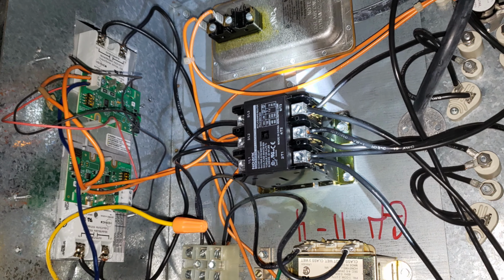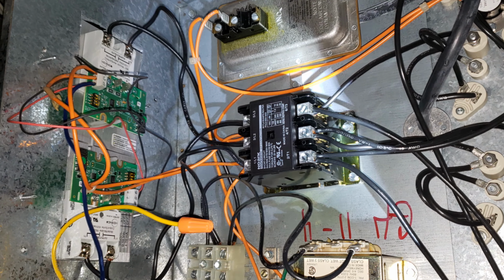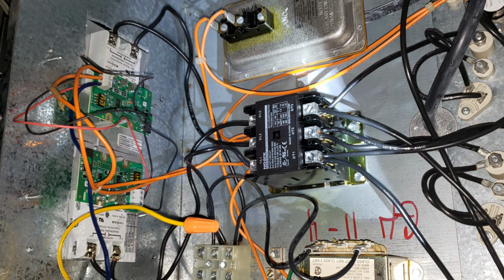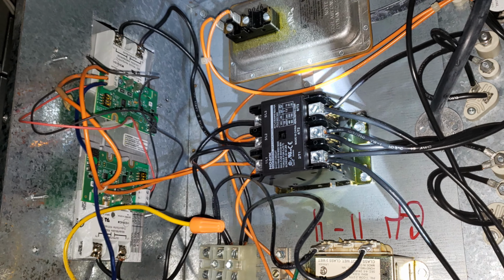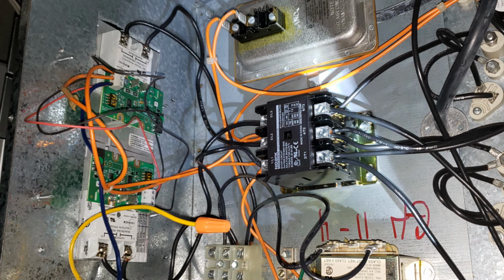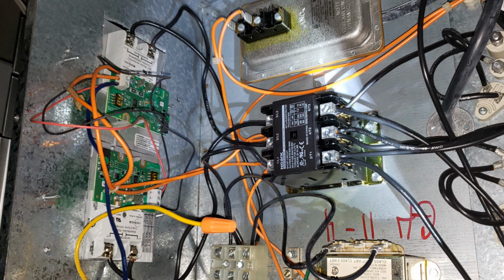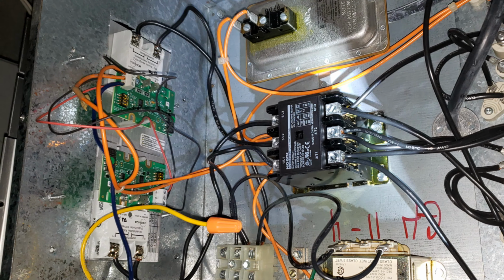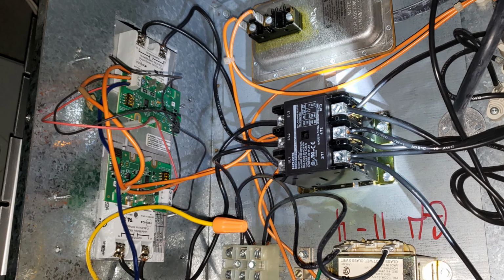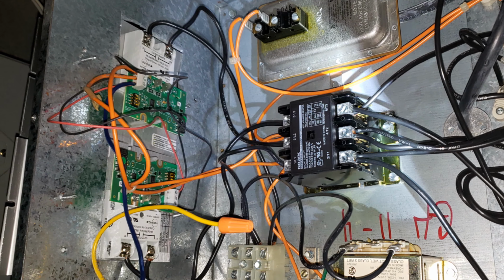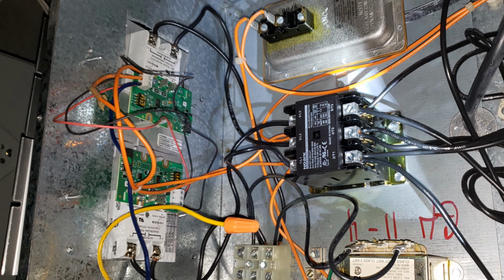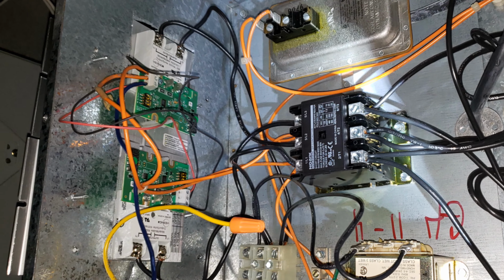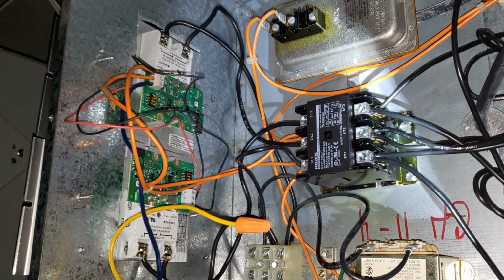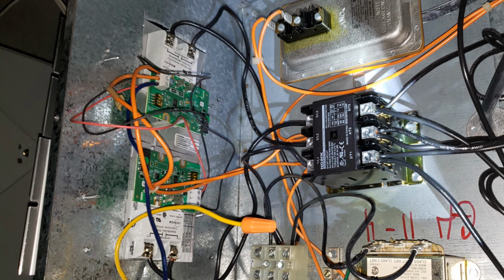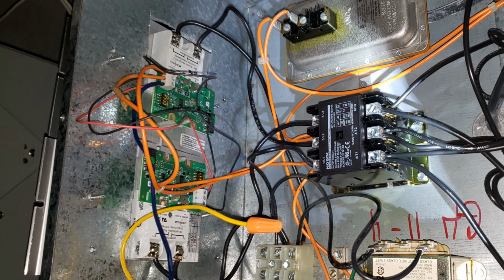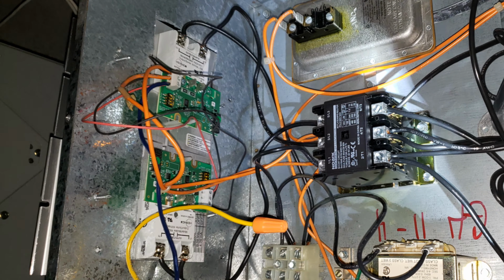So what should happen is that SCR should be modulating the heat through there, so it actually controls a regulated pulse to modulate the amperage running through those heaters, so that if we don't want to send 100% of its kW through there, so if they're 5K each, say we could modulate it down to where they only produce, say, 2K each at a time, and we can fluctuate that up and down as needed.